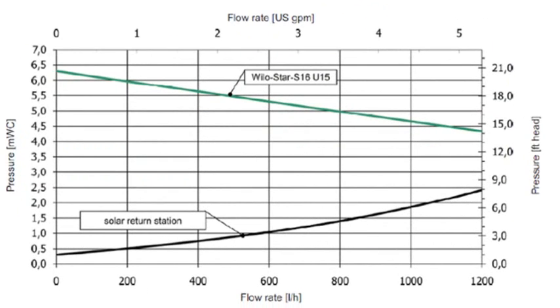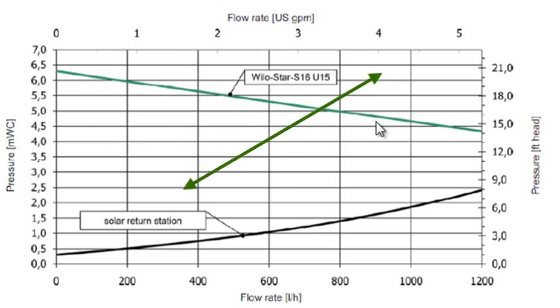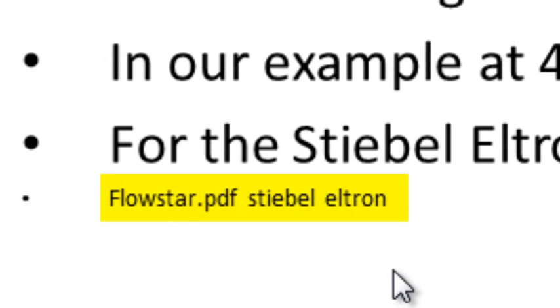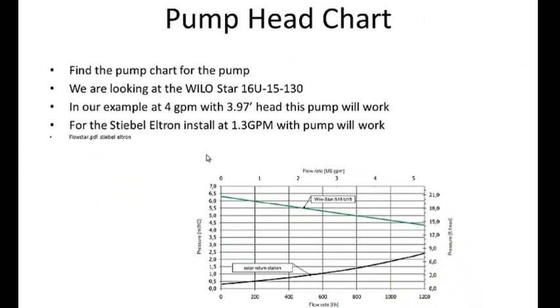I pulled up the Stiebel Eltron pump — the Wilo Star pump in the Stiebel Eltron system. Looking at their flow rate chart with gallons per minute on top and pressure on the side: if our worked example was at 4 gallons per minute with a head pressure of 3.97 feet, I go to 4 gallons per minute and see that I need to overcome about 4 feet of head. The green line tells me this pump will be more than enough to handle it. The Stiebel Eltron will work as low as 1.3 gallons per minute, which it was ideally cut for. That's how we calculate the pump sizing.